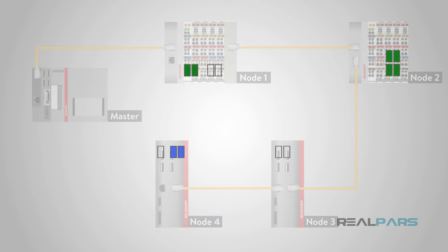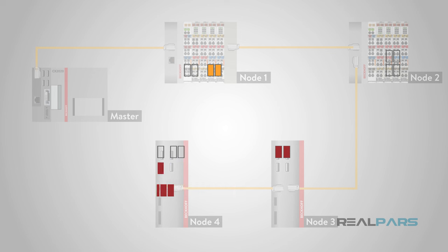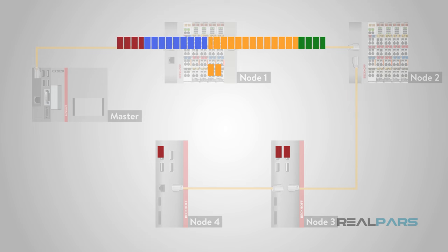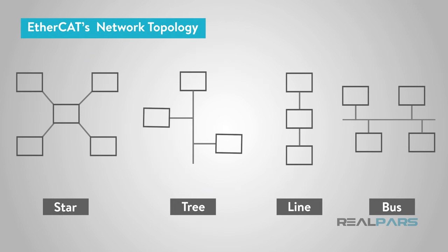Yet another advantage comes in the form of network topology. Many different network topologies may be used within an EtherCAT network. Because it utilizes Ethernet's full duplex layers, the EtherCAT slave will automatically return the frame to the master with an open port detected downstream, essentially self-terminating. Ethernet star topology is simple and can be used, but EtherCAT networks can extend well beyond that with a tree, line, etc. It can also be used in a fieldbus-type system using Ethernet hardware, giving incredible flexibility for your EtherCAT network.